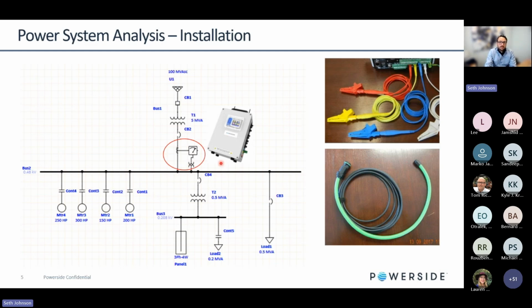And to install it, like most meters or analyzers, you need access to a voltage source as well as current source. So here on the right here, I've got an image of essentially what our voltage clamps look like. These are fused alligator clamps that you would put on A, B, and C phase, and so you're looking at the full three phases coming in, as well as neutral and ground. Now, if this is a medium voltage or even a high voltage application, we would connect these through PTs, of course. Most applications in medium voltage and high voltage have PTs available, which usually bring voltage down to 120. And then we just simply program that ratio in the recording device, the PQube3 here, so that we're getting accurate information.